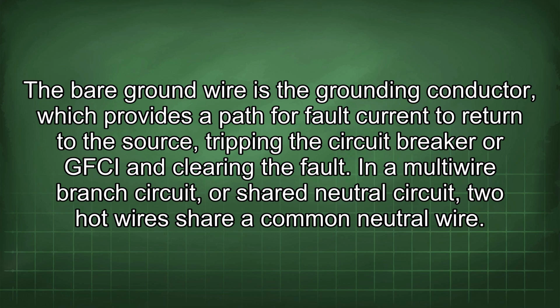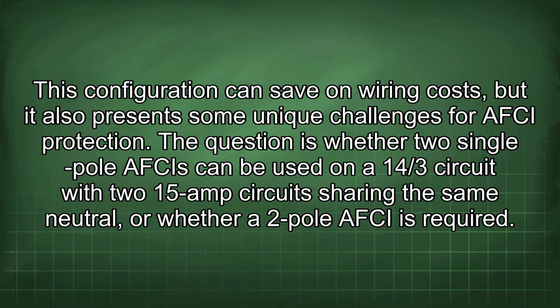In a multi-wire branch circuit, or shared neutral circuit, two hot wires share a common neutral wire. This configuration can save on wiring costs, but it also presents some unique challenges for AFCI protection. The question is whether two single-pole AFCIs can be used on a 14/3 circuit with two 15-amp circuits sharing the same neutral, or whether a two-pole AFCI is required.